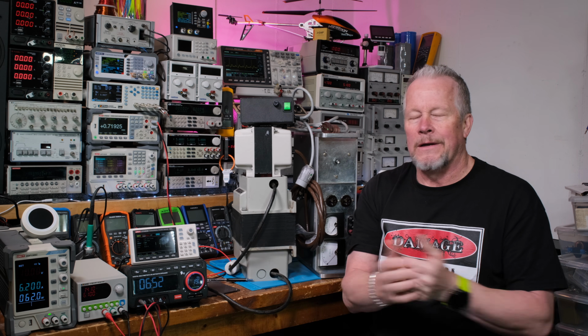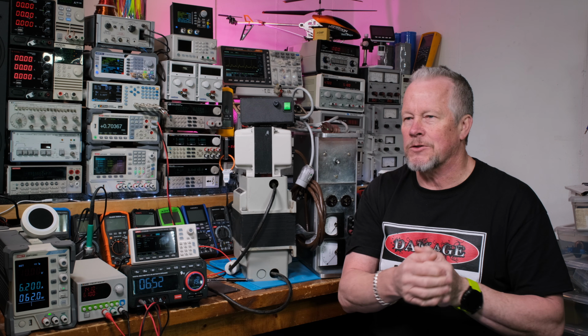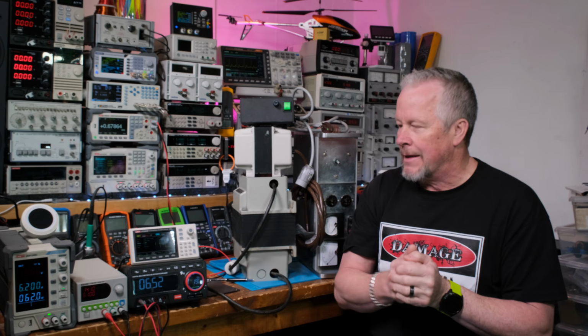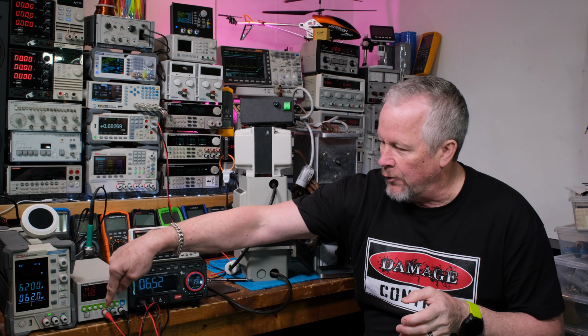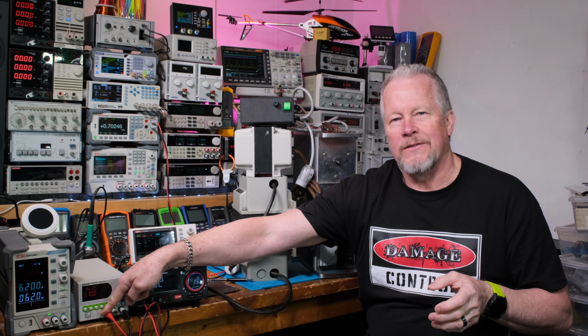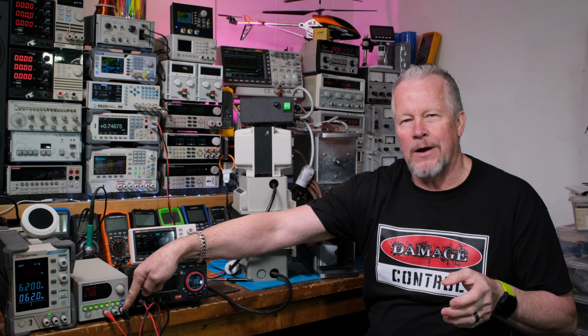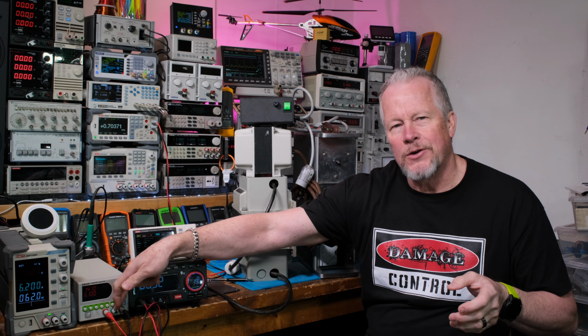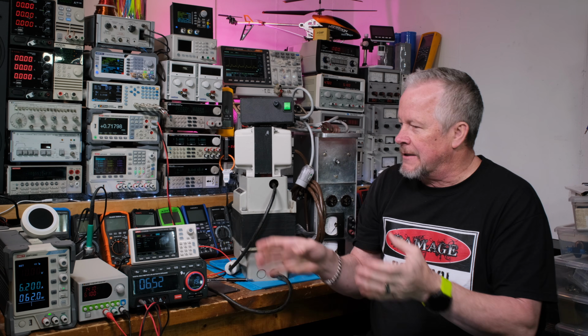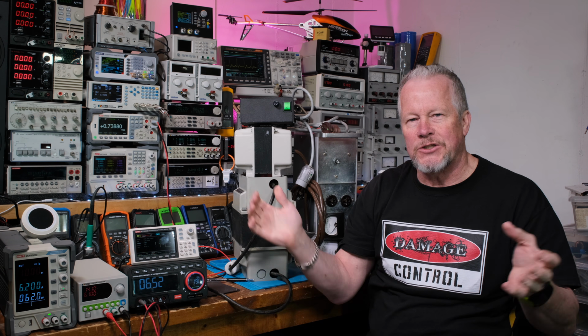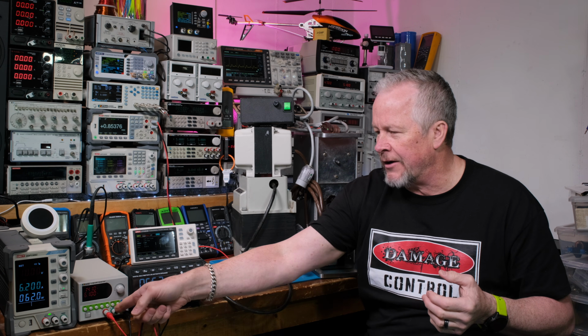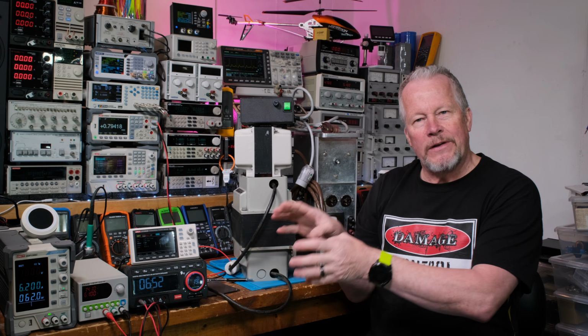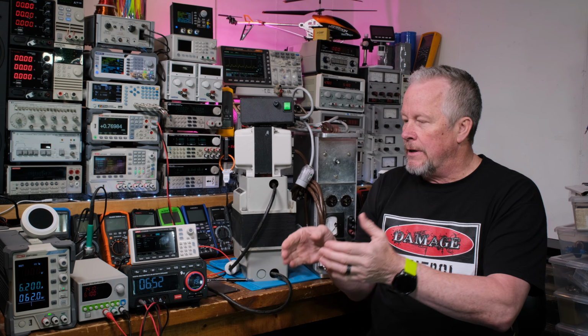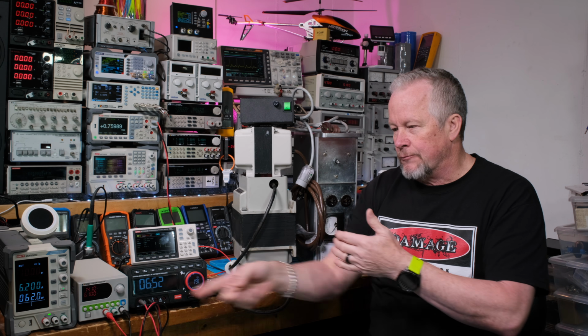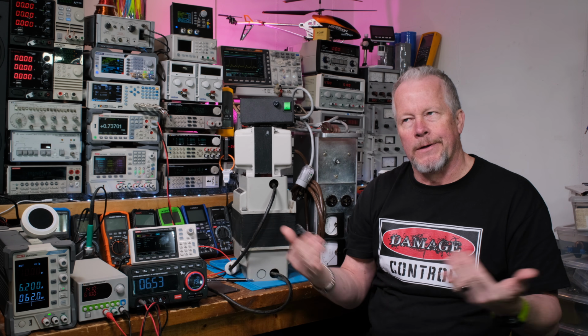The word ground just covers so many different things. On DC power supplies, we have a red and a black, so we think of it as hot and return, or hot and ground. But then there's this green terminal in between - it's a chassis ground, because again, metal box, they're all tied to chassis. You could take that green, tie it to red, so you have a negative voltage out, and your positive is referenced to chassis, to ground.